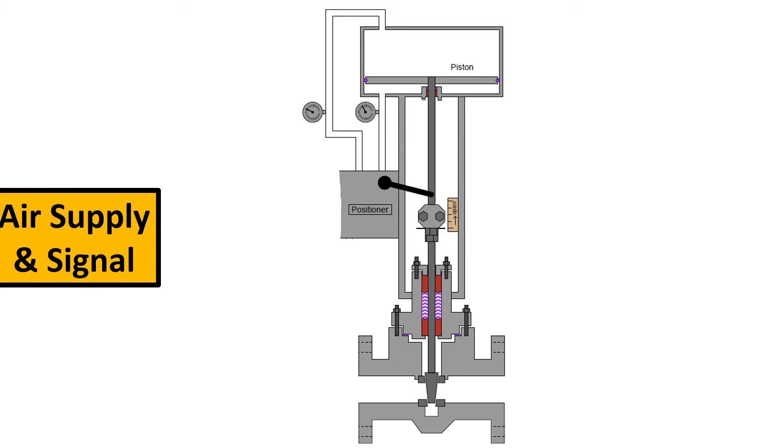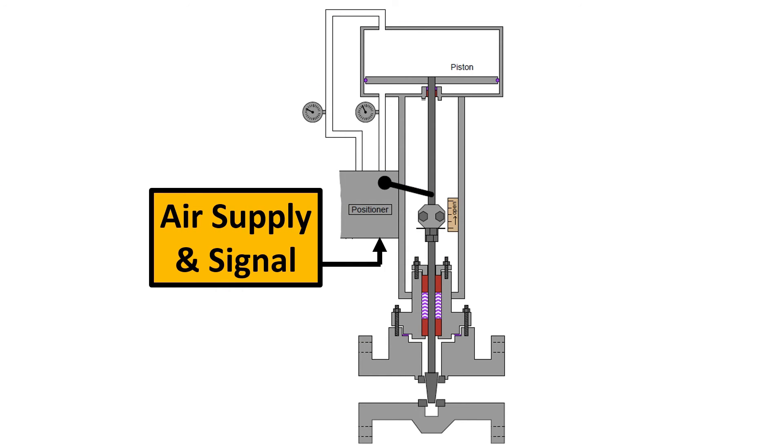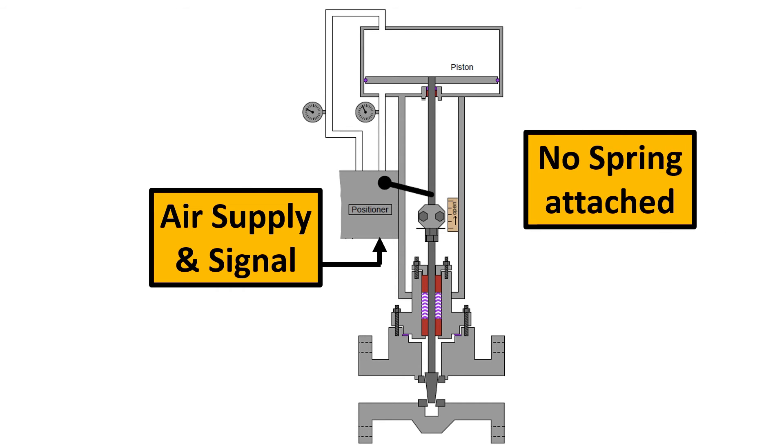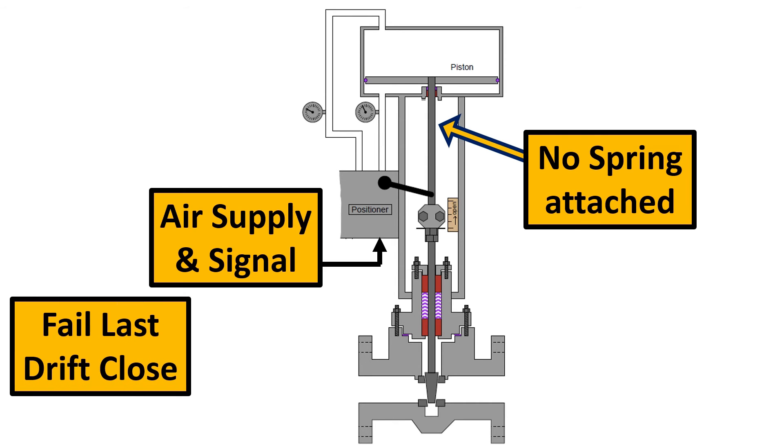So here if you see the air supply is going to come from here and the air supply is going to rotate the piston or basically move the piston but there are no springs attached to it. Do you see that? So what is going to happen here is if you want fail last drift close, drift meaning eventually it will lead to close. How? Because of the fluid flow.